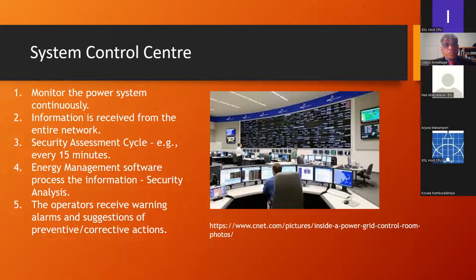Then you need energy management software to process that information, essentially to perform security analysis. The outcome of the security analysis is a set of alarms, if there are any, and the operators receive these warning alarms on the consoles in the control center with suggestions of preventive or corrective actions. Preventive action is when everything is okay, the steady state is okay, but if any of the contingencies in the list of contingencies occur, then the system is going to have some issues. So it's an early warning before that contingency happens.